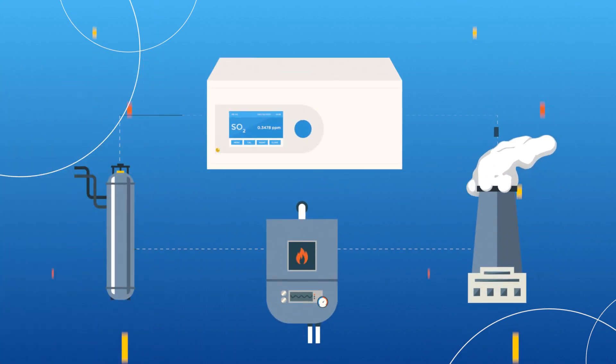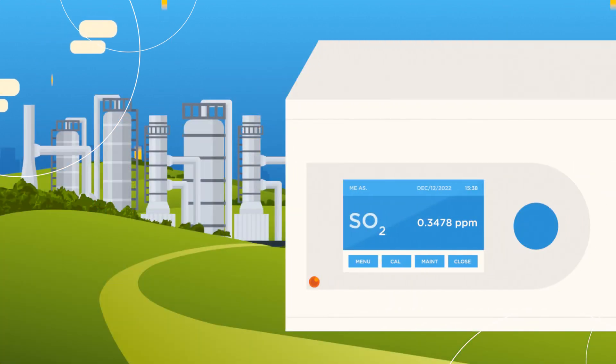Sulfur dioxide analyzers use ultraviolet absorption technology for detecting concentrations of these gases in heater or boiler flue gas and process gas streams. This helps control sulfur dioxide release to keep them from harming plants and animals through its acidifying effect on the environment.